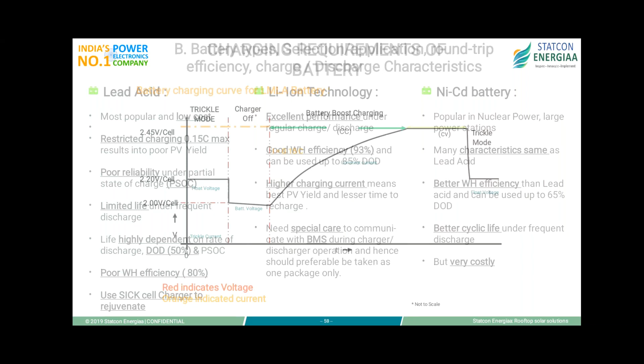This is a typical battery charging curve. I'll run through this, as it shows the CC/CV charging we all know. But if you really look at the graph, there are many more conditions to check when designing a charger, because you have to keep it at a certain level, then go to a certain voltage, and come back to a certain voltage, which is quite complex. So if you are having a lead acid system, it requires this profile to be followed.